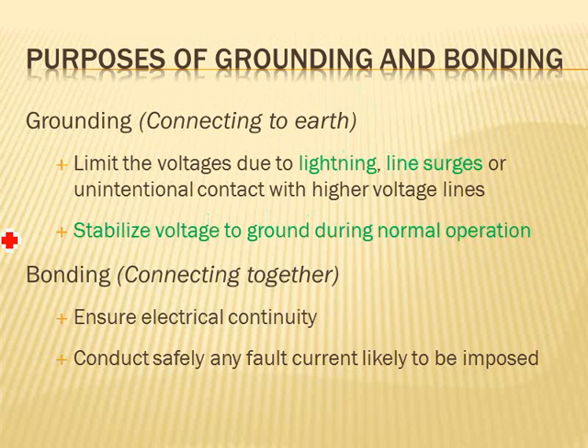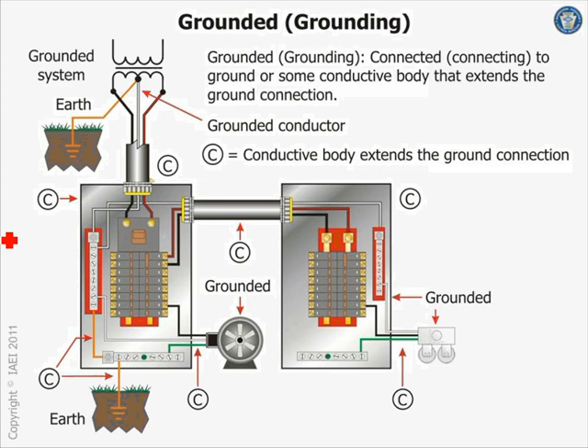But when we ground the system, we do the opposite. We want that path to be so easy. Grounded, bonded to everything metallic. So if somebody accidentally moves this fixture and a hot touches the ground, immediately the ground fault will wake up and say, yep, there's a ground fault, go fix it. That ensures electrical continuity and conducts safely the current imposed on them.